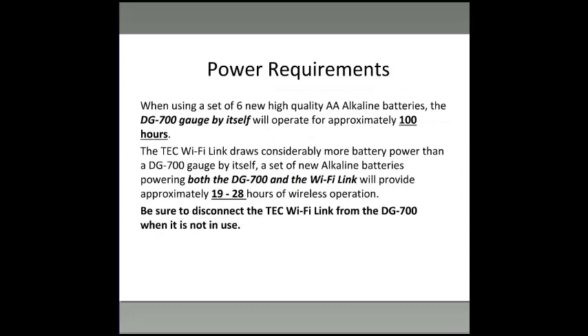I mentioned the power requirements earlier - the DG700 gets 100 plus hours, it seems to go forever. Word of caution: if you have a lot of DG700s with your company and they're sitting, it's best to pull the batteries out and store them without batteries in. The worst thing that can happen to old DG700s is letting them sit with batteries in them. Get the batteries out, and just put them in when you're using the device. You can expect about 100 hours of solid runtime on a good set of alkalines.